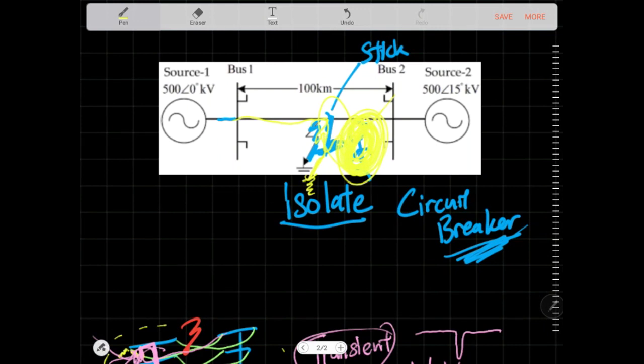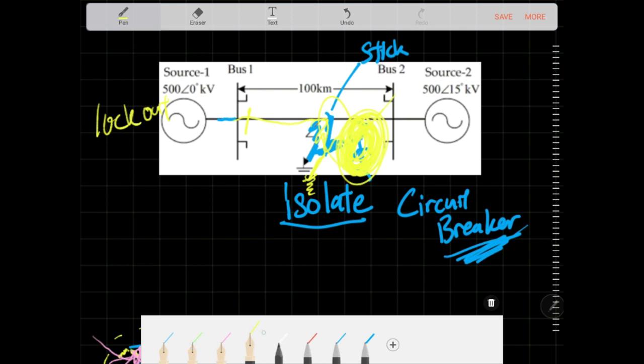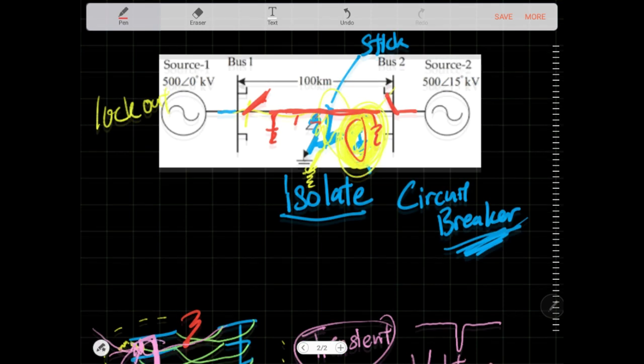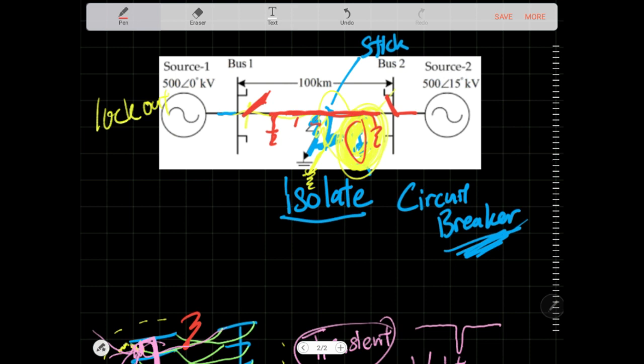When you isolate the line, this is called a lockout — you open the breaker and keep it open so the line is isolated and de-energized. You also need to earth the line first to drain out any residual current, because residual current can still be dangerous. Once everything is earthed and safe, you remove the fault, then unearth the line and energize it back.